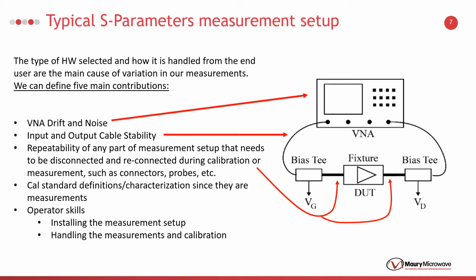Fourth, calibration kits are mandatory tools for calibration. Unfortunately, there is no perfect calibration kit providing an excellent correction. For example, coefficient tolerances, physical deformations, and temperature changes cause errors. Fifth, the operator's skills and experience have a direct impact on measurements such as correct installation of equipment, and proper usage of adapters. The most common mistakes made when setting up a measurement are using too short or too long a cable, causing mechanical tension in cables and components, not supporting the heavy equipment in the measurement setup properly, and undesired signal coupling between sensitive components, to name a few.